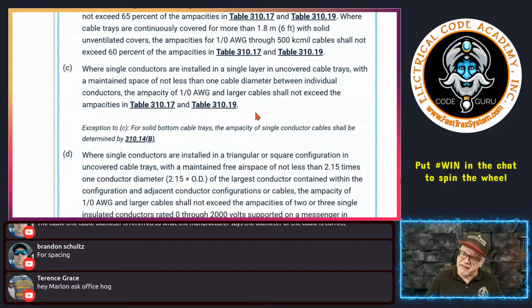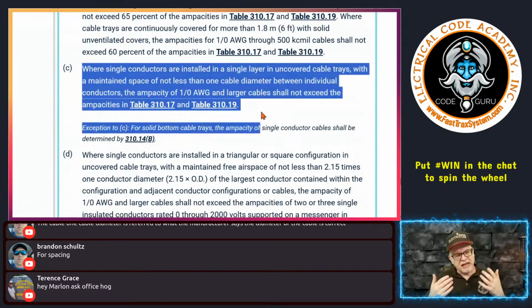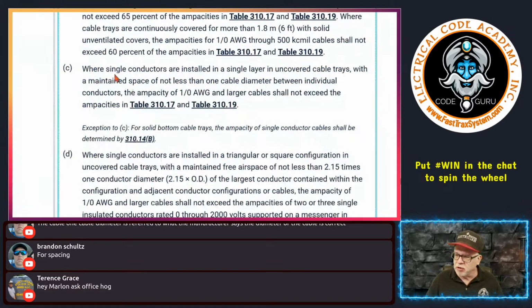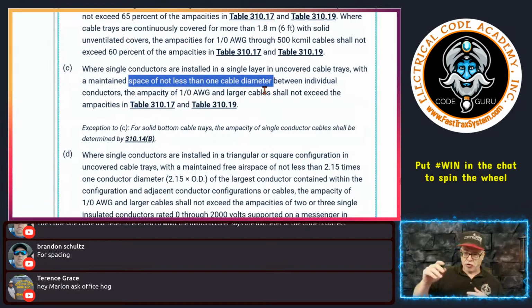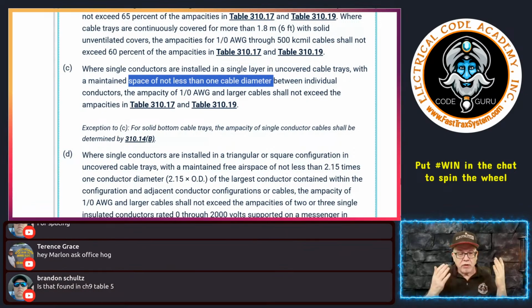But in this one, it says this three times, and it's frustrating because it talks about single conductors in a layer. Then it says they have to have a spacing of not less than 1 cable diameter. And you're saying, well, Paul, a cable is different than a single conductor. Not in this context, because if I've got to have not less than 1 cable diameter, what cable do I use? Is it a diameter of 1 inch, 2 inches, 5 inches, 6 inches, half inch, quarter inch? You get what I'm saying?